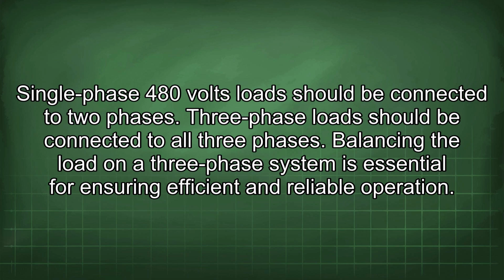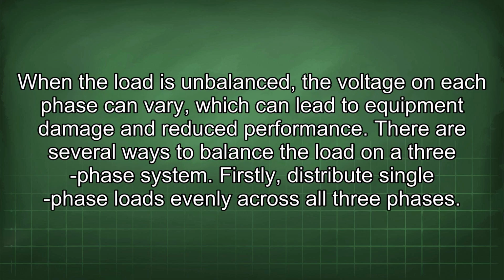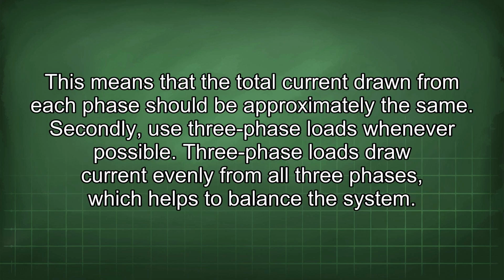Balancing the load on a three-phase system is essential for ensuring efficient and reliable operation. When the load is imbalanced, the voltage on each phase can vary, which can lead to equipment damage and reduced performance. There are several ways to balance the load on a three-phase system. Firstly, distribute single-phase loads evenly across all three phases. This means that the total current drawn from each phase should be approximately the same.